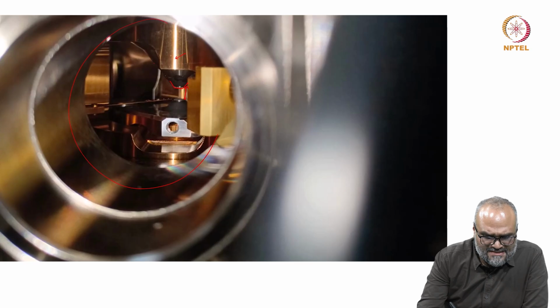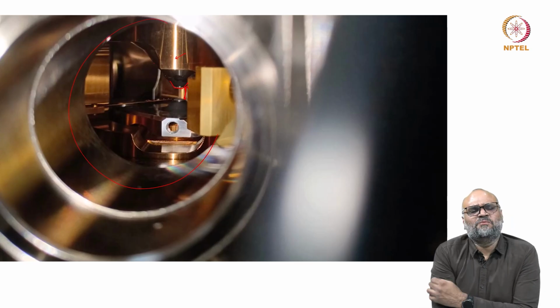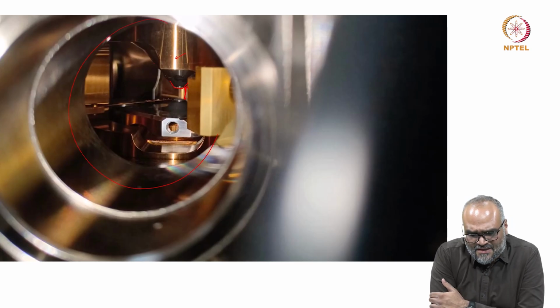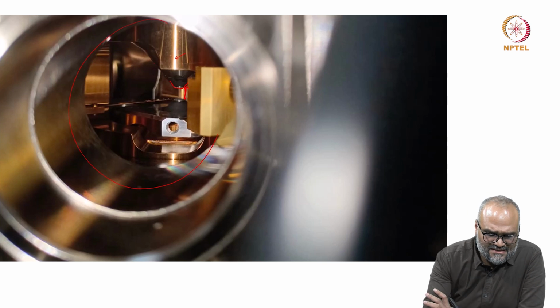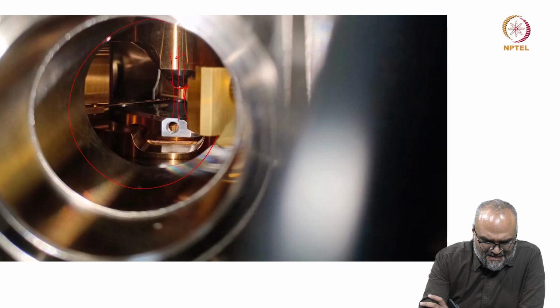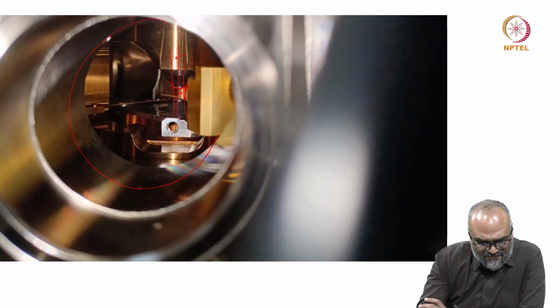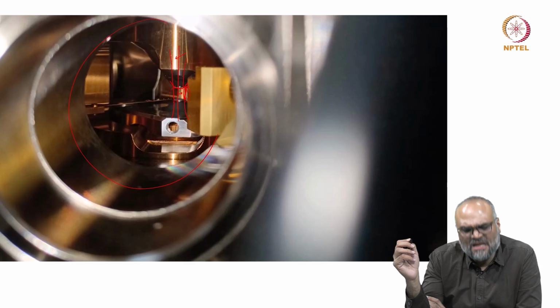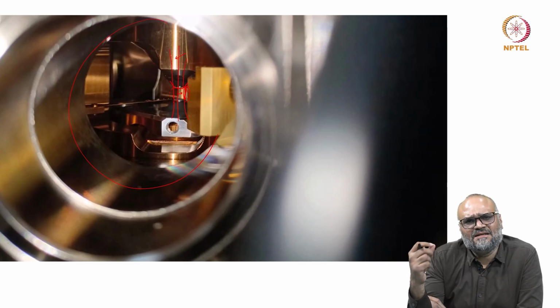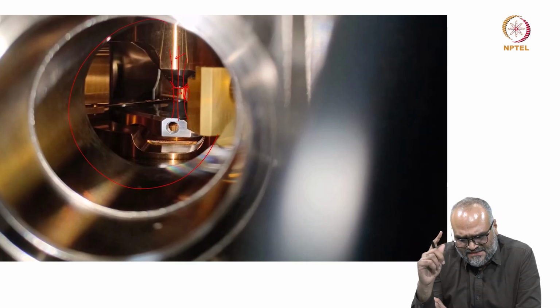Now, why is this pole piece design and the pole piece gap important? One important parameter here is that the magnetic field strength is going to vary as I go radially outward from the optic axis. But when I have this kind of a pole piece, the field distribution would change because there is a gap here. Now, this in turn introduces some lens aberrations. This is the first thing.